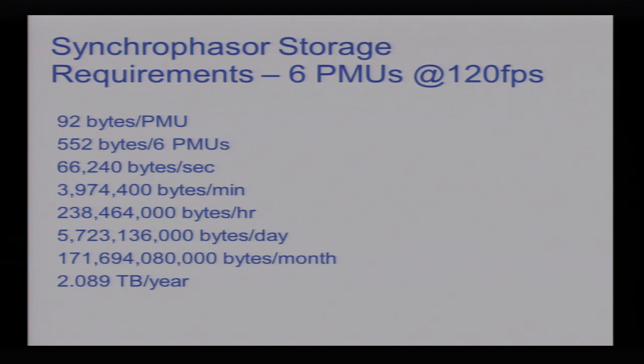So inside the message, there are trigger bits. The PMU says, hey, I see an overfrequency. Hey, I see a line out. Hey, I see an overcurrent. So by carefully analyzing the trigger bits in the message, I can be judicious as to how much data I choose to save in my storage system.